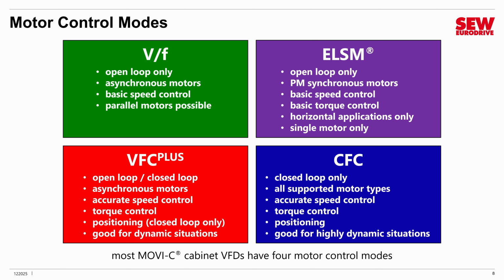And the last mode, which is the very best mode and the preferred mode that you should use if at all possible, is CFC mode, which stands for Current Flux Control. It is a closed-loop only mode, so you must have a feedback device, but it works with all motor types. It gives you very accurate speed control, good torque control, excellent positioning, and it's very good for highly dynamic situations. Many of our field engineers at SEW-Eurodrive recommend you use it if possible because using it can solve many problems. So these are the 4 modes available with MOVIDrive technology, MOVIDrive system, and MOVIDrive modular.